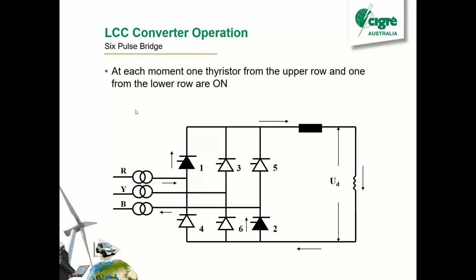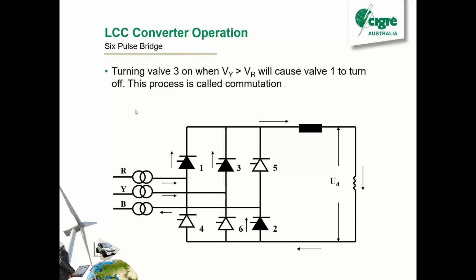And then we'll move further through the wave. We'll turn on valve 3. We do this 60 degrees into the cycle of the AC wave. What that will do is we've now got 3 valves conducting. We've got 1 and 3 sharing the current. We've got current coming in on red and yellow, and then all coming back on 2.